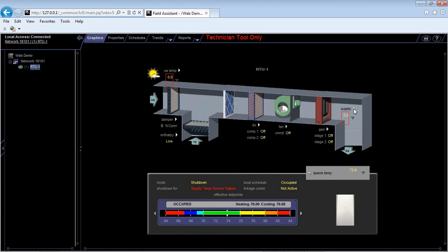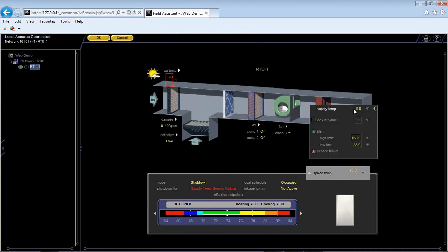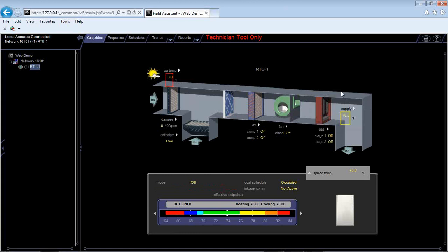But I'm still in shutdown mode because I have a supply air temperature sensor failure, because I don't have one wired in. If I hit this little expandable button here, it will allow me to fake the unit into having an actual supply air temperature reading. So I have this little checkbox where I can click lock value at. Let's say I want to lock this at 70 degrees. I hit OK. Now I'm going to think that I have a supply air temperature of 70 degrees. So my supply air error just disappeared because I think I have 70 degrees in that spot. Now you can see I'm off. That's just a minimum off delay.